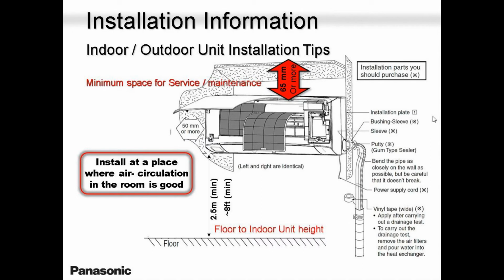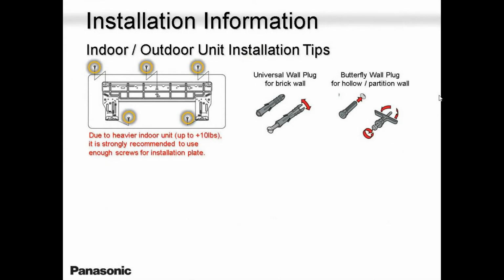Obviously, as an installer, you may have come across in your life that you installed an indoor unit above a window or above a door, and during summertime, it drips a lot of water. That's not the best place to put a unit, because the heat from outside meets the cold inside, and that's where you get a lot of condensation. So keep that in mind all the time.